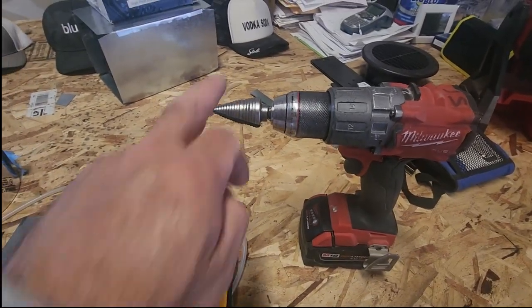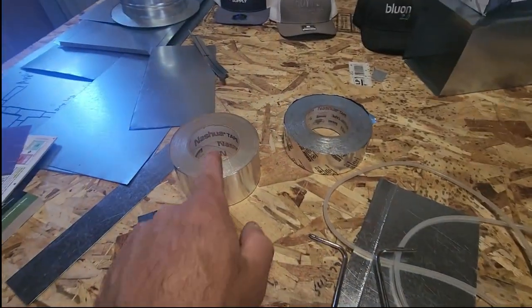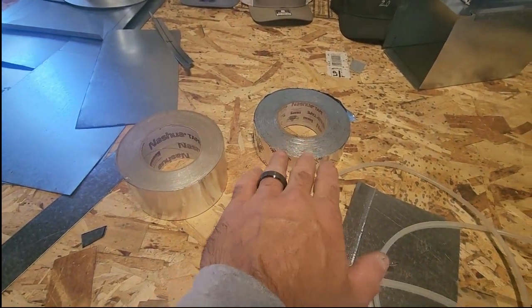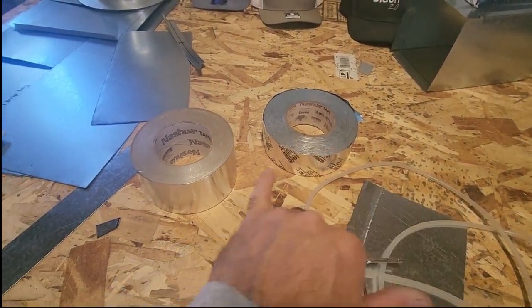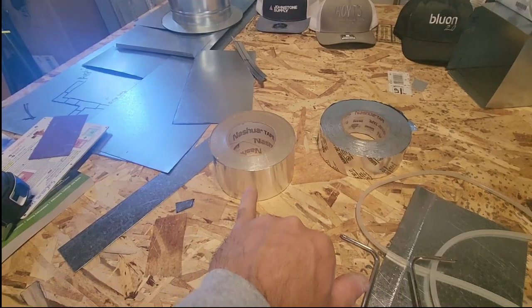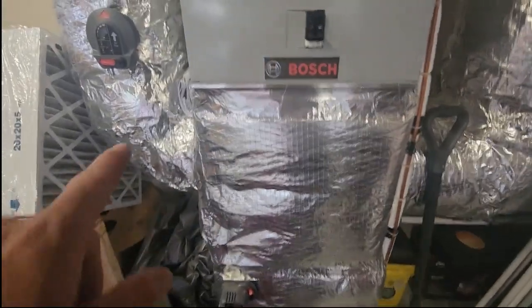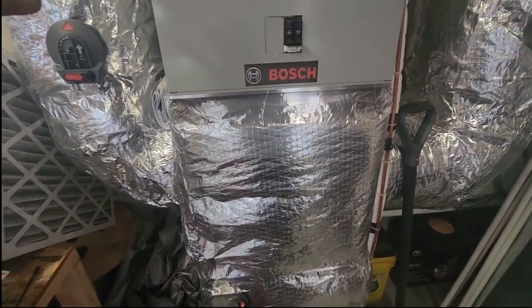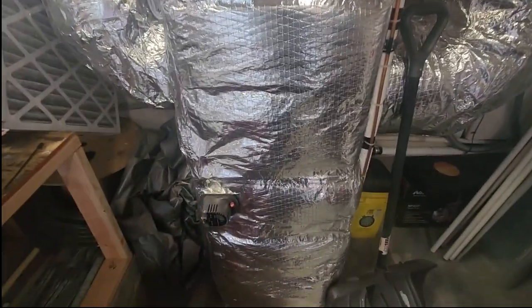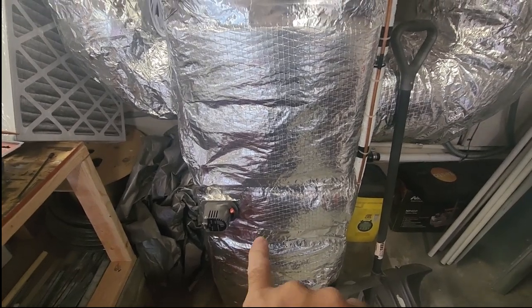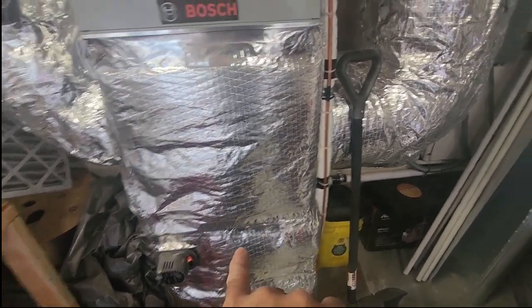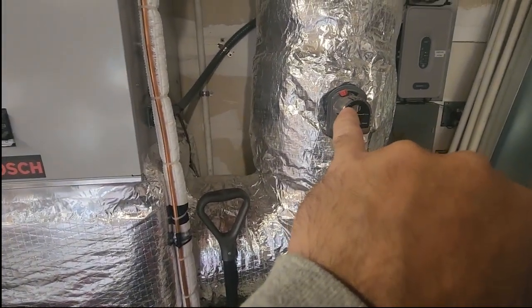The last thing you're going to need is something to drill a couple holes with. I also have tape to tape my holes. They make plugs, but it's my system, so I'll just tape my holes and tape my insulation back. Let me show you the orientation here again on my system. I have my bypass here. I'm not worried about it because we're checking total static of the supply and return. There's the one damper there, and the other damper that goes upstairs, the supply run.